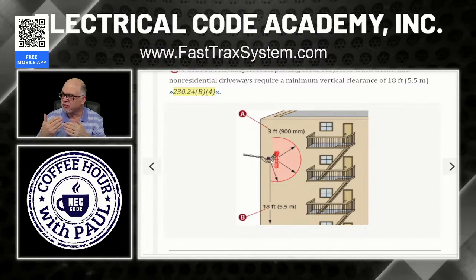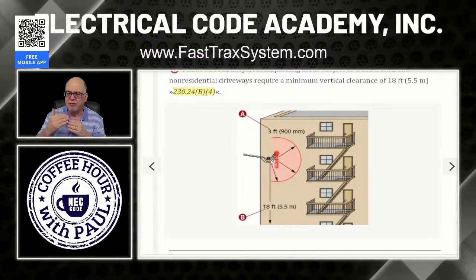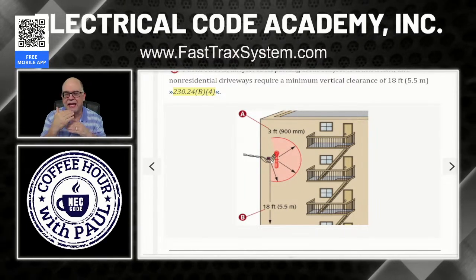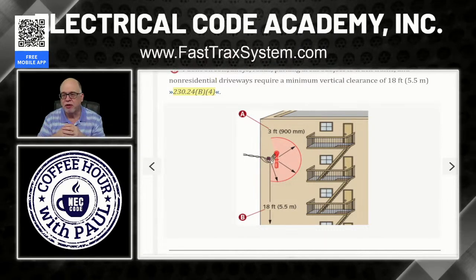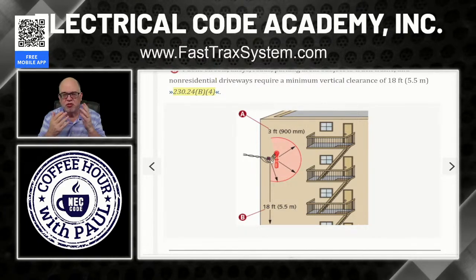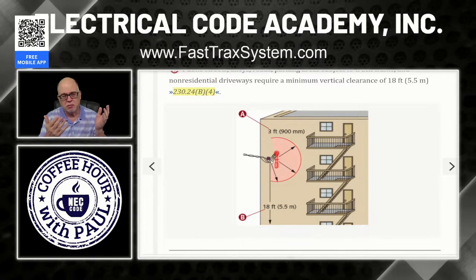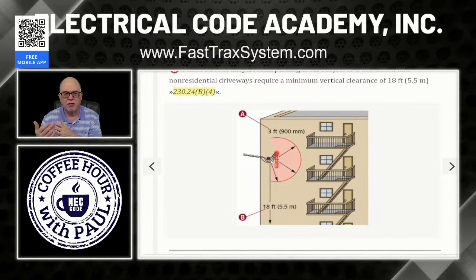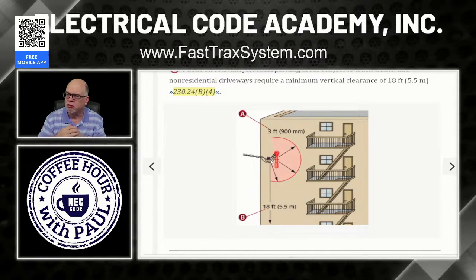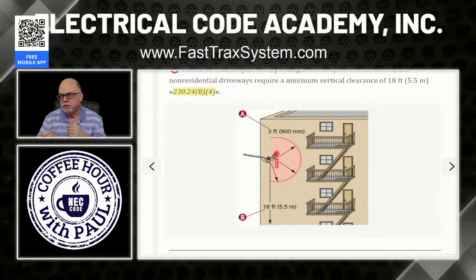So I think it's an important distinction that most people won't argue anyway. They'll say, well, I'm just going to make sure that I put the point of attachment high enough that I'm going to meet 230.24, even if it's service drops, because they don't want the headache and the inspector who may or may not know the difference in 90.2 and whether this is covered or not. But also they're charged with something that if it's too low, then it's unsafe. And so they have to protect their what? The constituents of their community. They're public servants to the community. So at the end of the day, it becomes a compromise and most people just follow 230.24. But I thought it was important for you to understand the language in the code to differentiate.